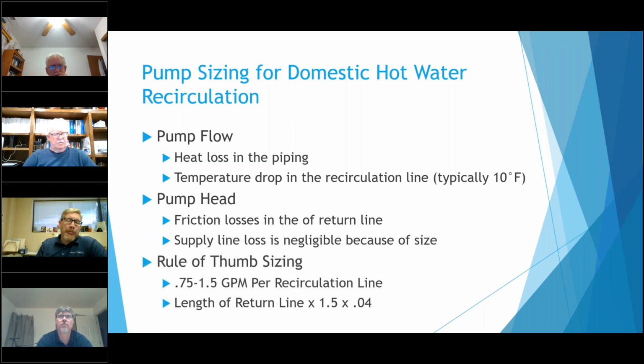Rule of thumb, a lot of times the recirculating line is only, like I said, 3/4 to 1.5 GPM per line. So if you'd have a system, it'd have like 4 or 5 different lines. You'd multiply. I would typically go with 1. So I need a pump that would do 4 to 5 GPM. And whatever the longest return line would be, you'd take that times 1.5 times the 0.04.